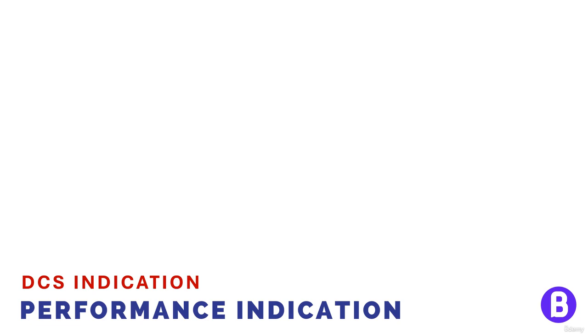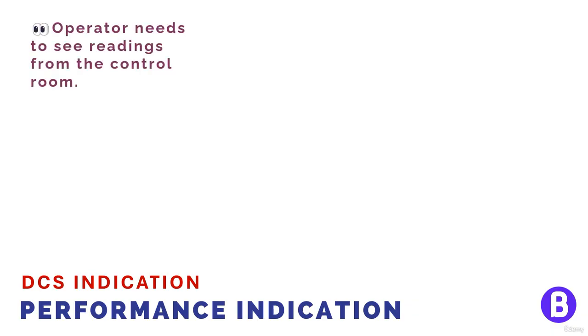The issue with field instruments is that they cannot be read from the control room. So this means that there should always be an operator in the field to track the reading. Although this may be applicable in case of startup, this cannot be accepted for most readings that need to be tracked during normal operation. That's why most instruments are transmitters that read the value and send it to the DCS in order to be read from the control room.